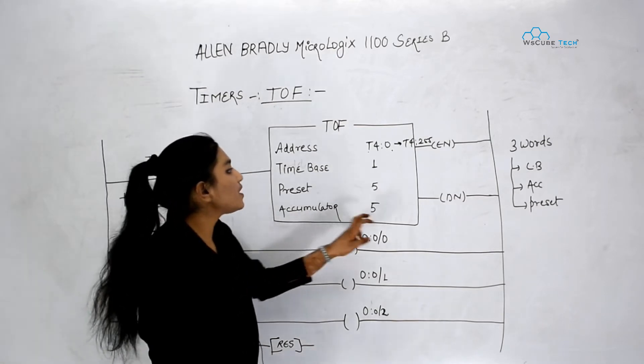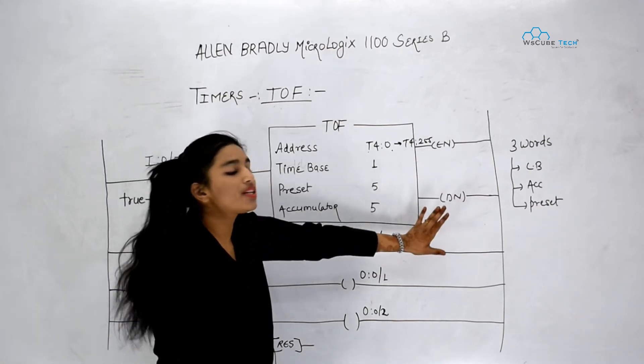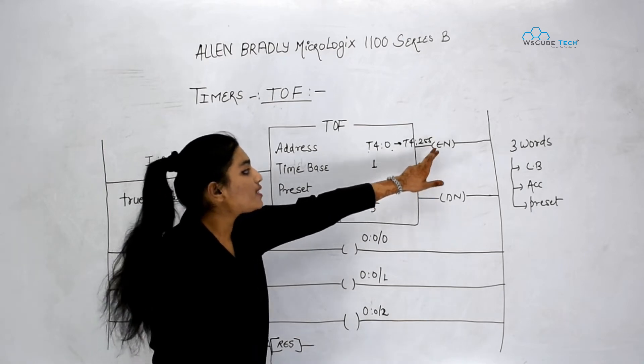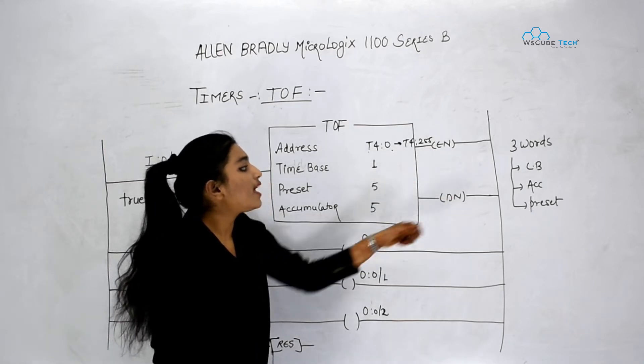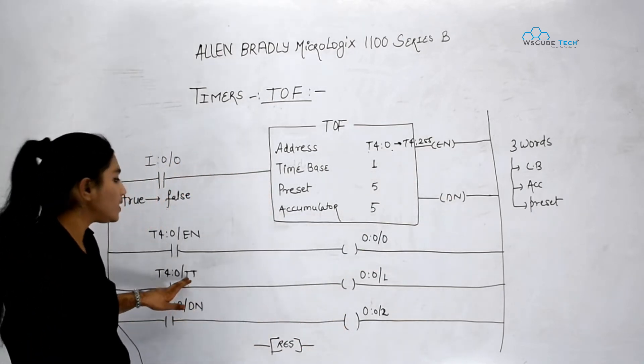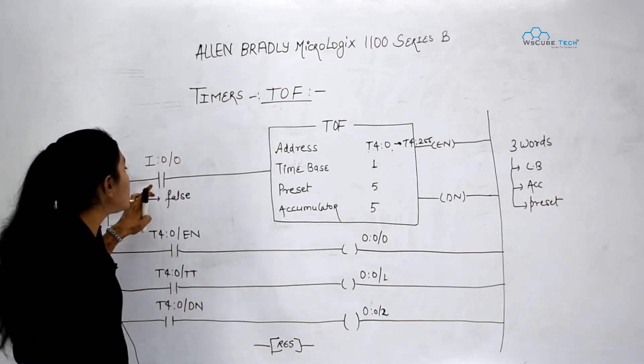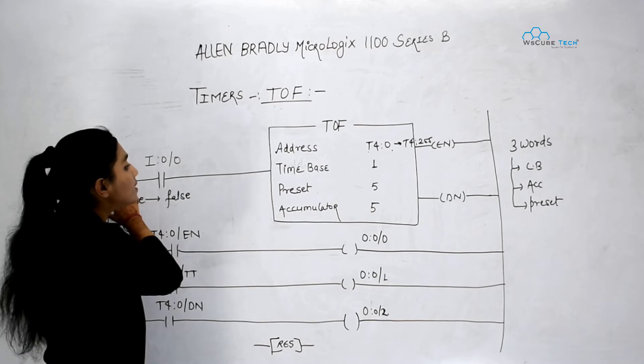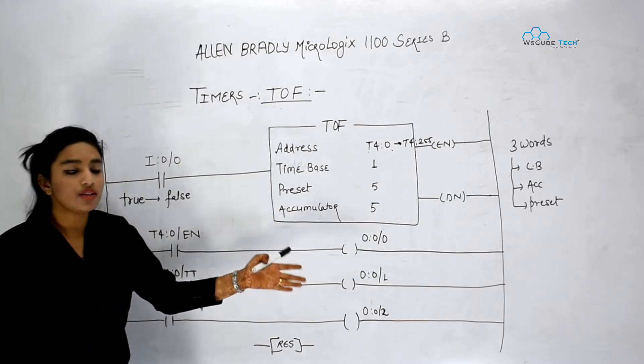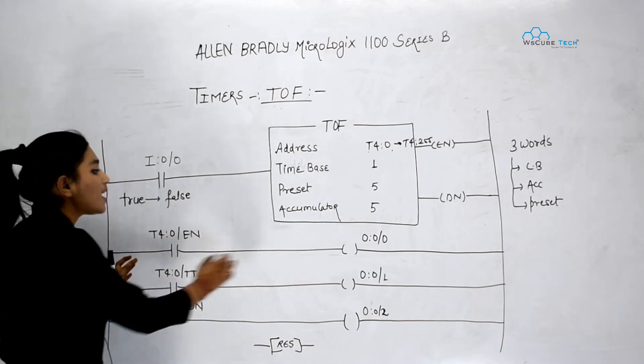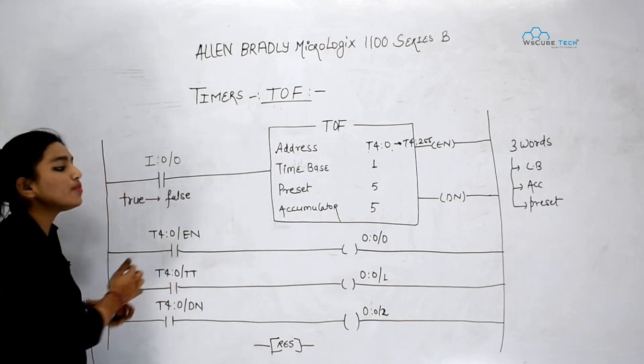Then in this instruction we have got three bits. These are known as control bits. One is enable bit, one is done bit and another we have got TT bit. So enable bit is 1 when my input is 1. It means when this rung is true that time enable bit will be 1 or true and the output which is attached to enable bit will be 1.